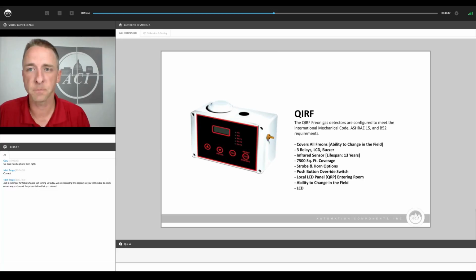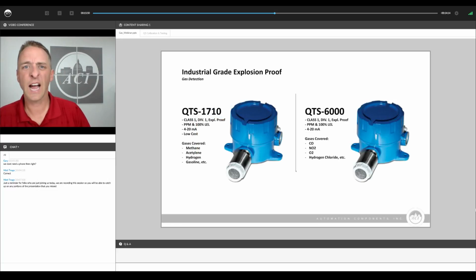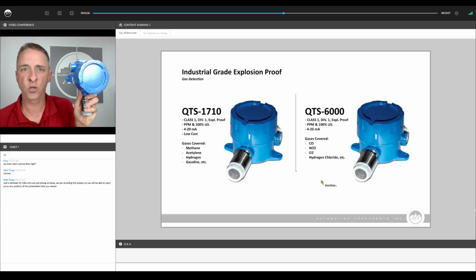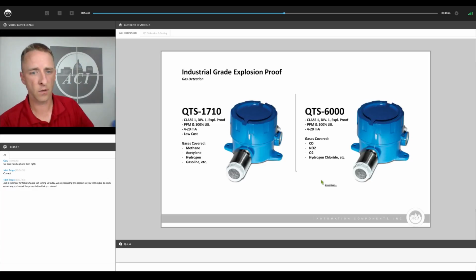Moving on to some of our high-end industrial grade explosion-proof toxic and combustible gas sensors. You see the 1710 series over on the left-hand side of your screen. This is for the hydrocarbon gases, and both of these units, the 1710 and the 6000, are without LCD, so these are a lower cost option. The 1710 is for the combustible gases like methane, hydrogen, gasoline, diesel, and things like that, whereas the 6000 series is going to cover your toxic gases like CO, NO2, oxygen, and ammonia, things like that. So these are Class 1, Div 1 rated explosion-proof enclosures. You can see these are a very sturdy, heavyweight enclosure to provide completely explosion-proof gas detection in these environments.